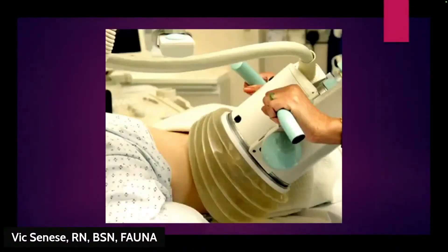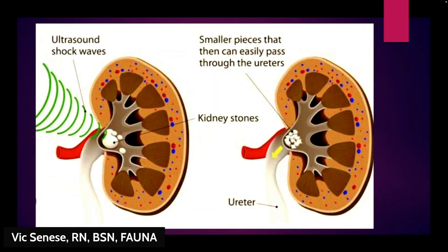That shockwave pad is filled with water, replacing the old bathtub. It's placed directly on the patient and they use gel to create what's called acoustical coupling — eliminating any air spaces. This diagram shows how the waves are focused right on the stone, with peak energy released at that target point, breaking it apart into fragments.